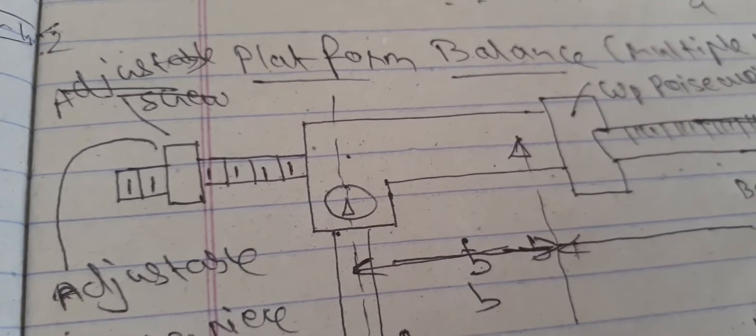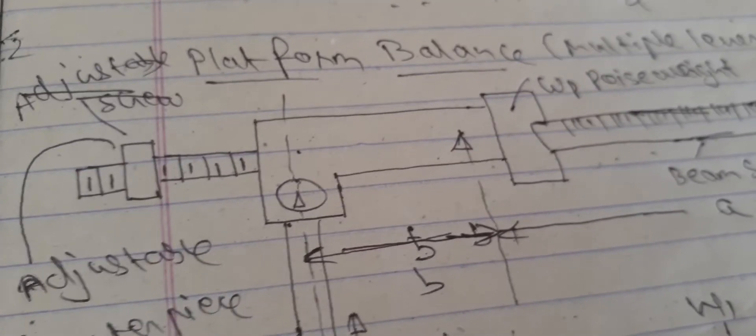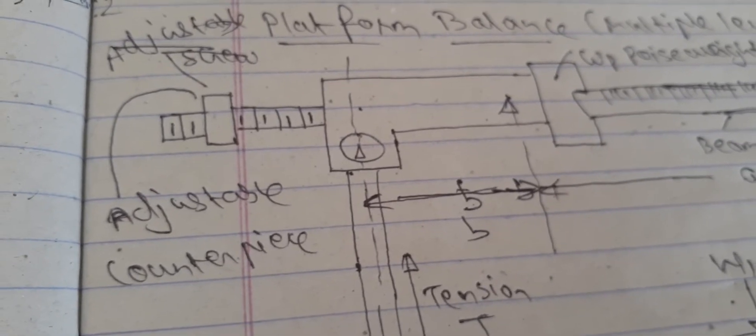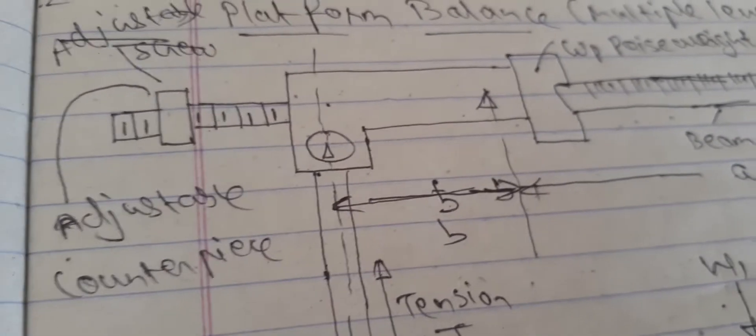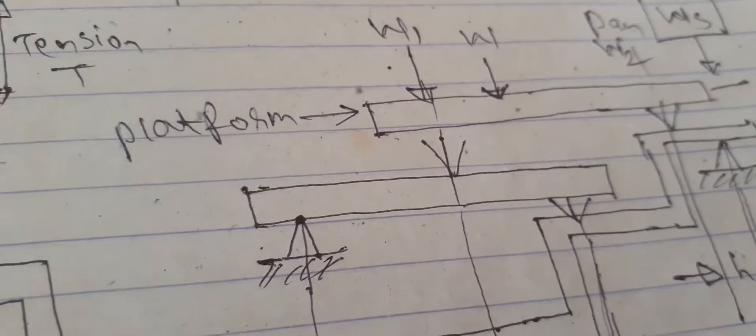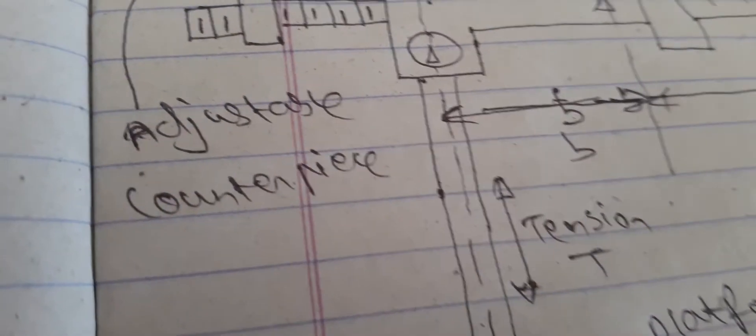Those are not suitable for measurements of large weights. When measurements of large weights are involved, multiple lever system which is shown in figure is used. In this system, the weight W is measured in terms of W suffix p poise weight and W suffix s weight of the pan.